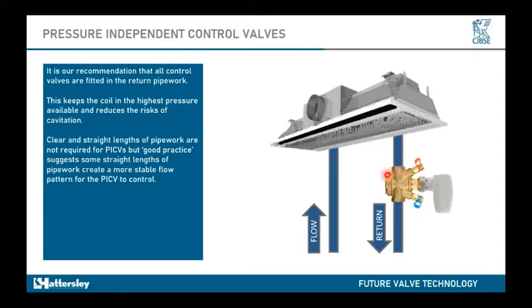You've got to remember, with the bottom and the top chambers within the DPCV differential pressure controller, there won't be any flow. Once it's filled, there's basically no water flow. So again, you could get particles forming inside those impulse tube connections and blocking them, and therefore reducing the pressure transmission to your chambers and effectively reducing the performance of your PICV.